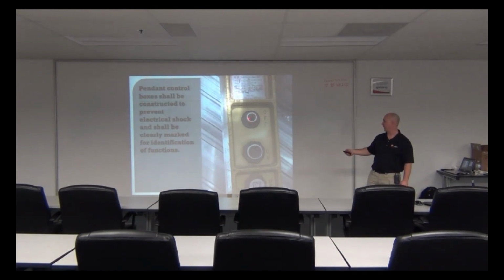This is just a button. I guess if you were to stick your finger in there, you could be shocked. But you want to make sure the casing's intact too, and not falling apart or loose in certain places. So at a crease or seam where they put it together, if that looks like it's coming apart a little bit, it would need to be replaced. Contact whoever serviced the crane, and they'll come out and put a new one in.